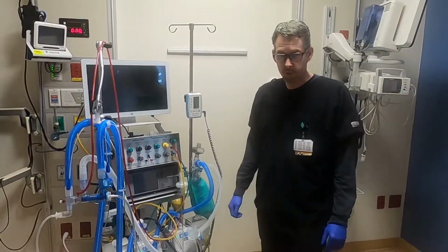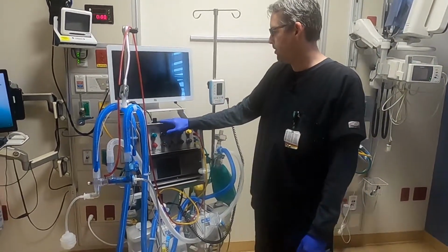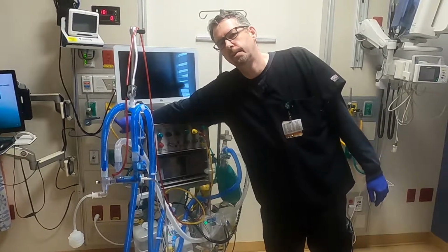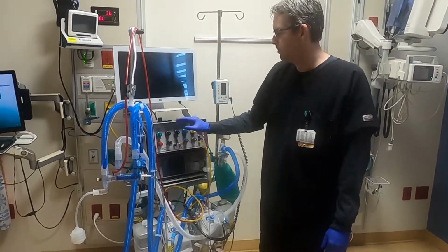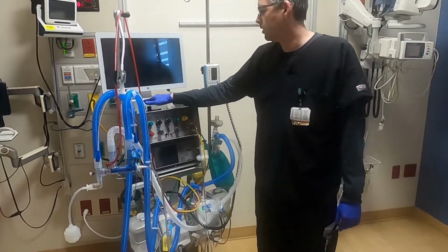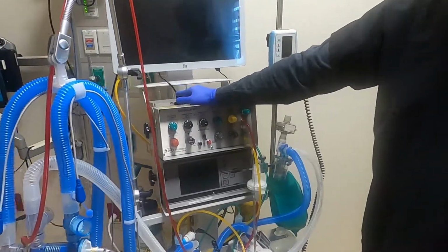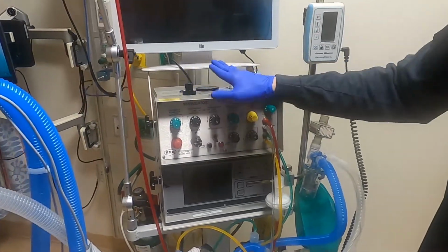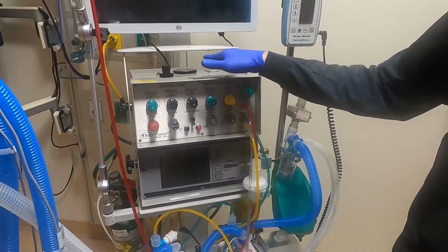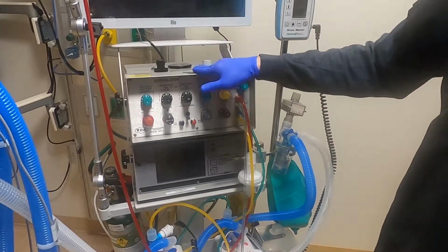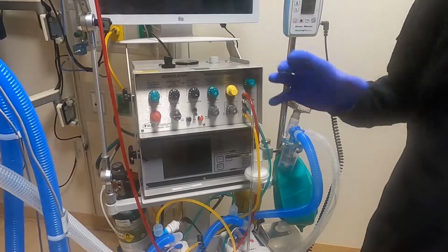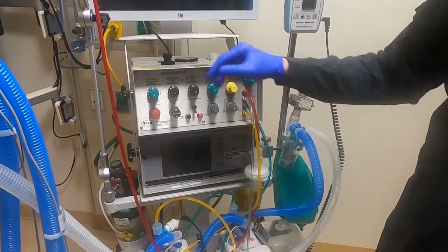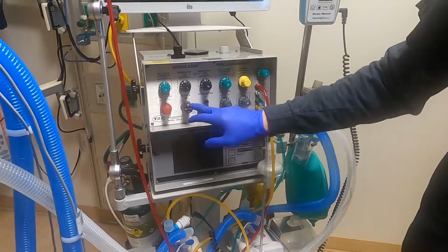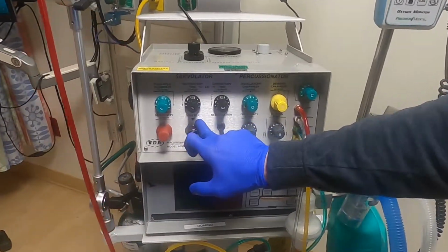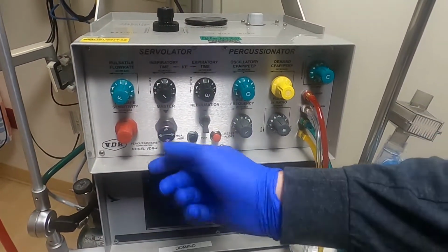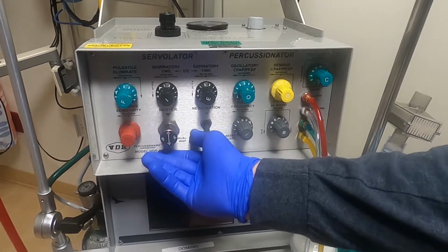Okay, we're going to turn on the machine. First thing we do, we have it connected to the gas source over here. We are going to turn on our working pressure, and that's going to be dependent on the patient size. If it's a neonate, it's going to be about 30. If it's a pediatric, 35, an adult, 40. Sometimes, depending on the vent settings, you're going to need more or less of that. Here is the on-off, the master switch. So to turn the ventilator on, boom, we're on.